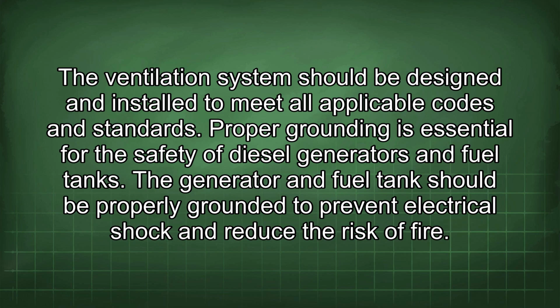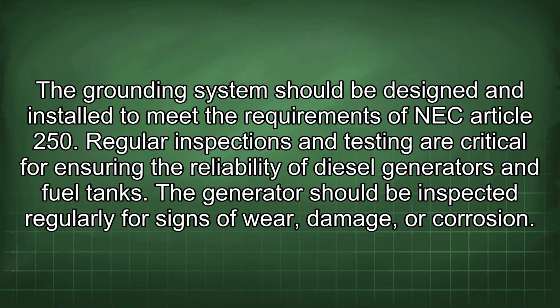Proper grounding is essential for the safety of diesel generators and fuel tanks. The generator and fuel tank should be properly grounded to prevent electrical shock and reduce the risk of fire. The grounding system should be designed and installed to meet the requirements of NEC Article 250.